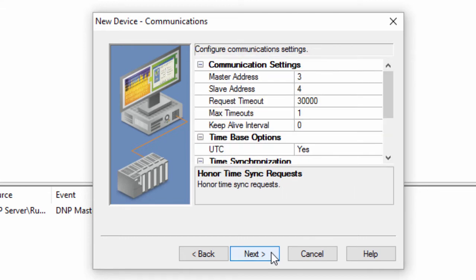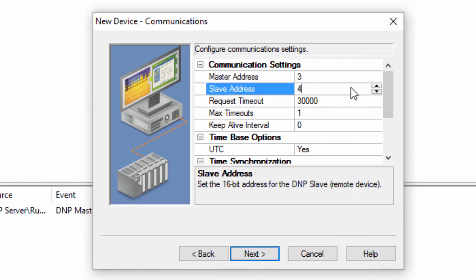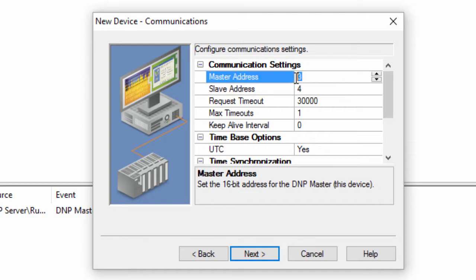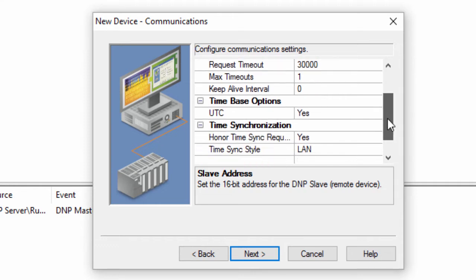Click Next to specify the communication settings for the device. Make sure to enter the correct master node and slave node addresses for your stations. In the DNP protocol, the slave may send a synchronization request to the master to synchronize its clock. There are two options, LAN and Serial.